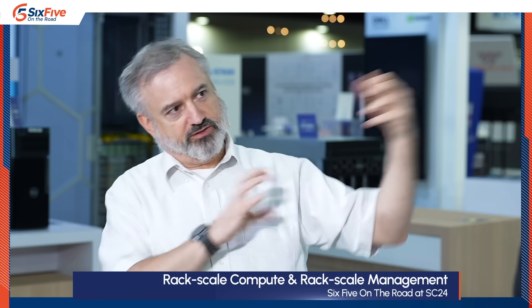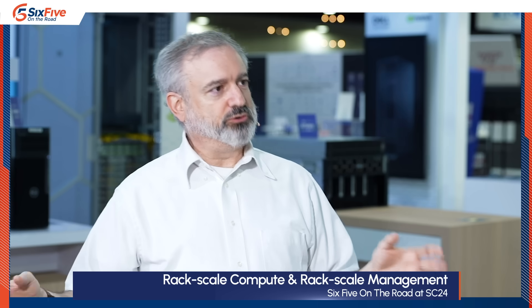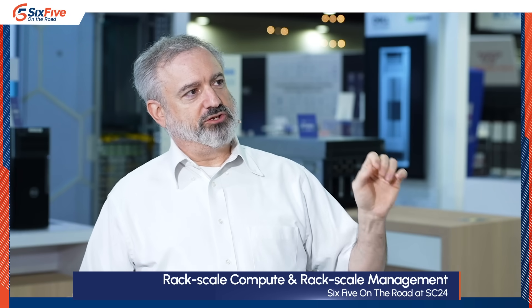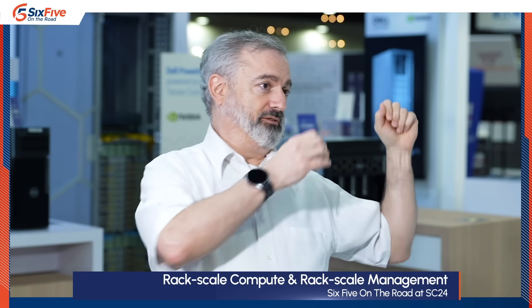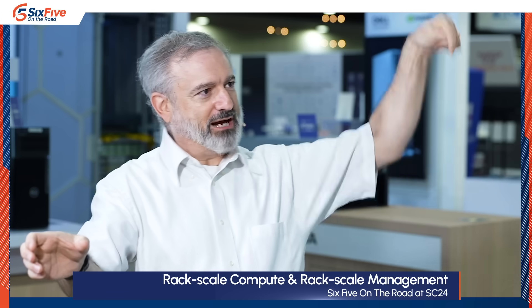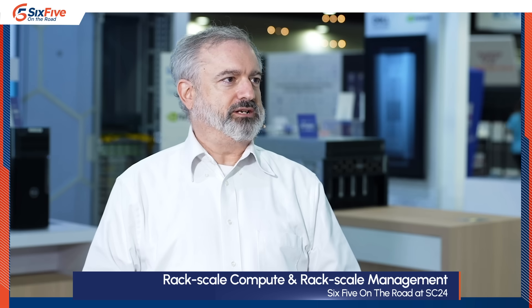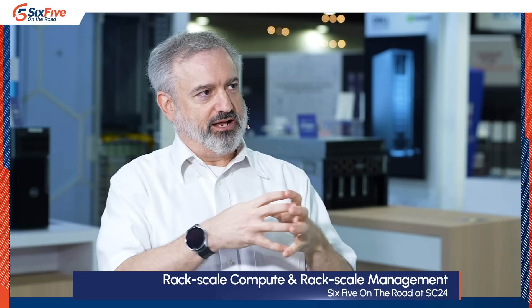Because all of our servers have thermal sensors, we're able to give a thermal view of the front and rear of the rack. But what's really important is: if you've got 10 racks of liquid-cooled gear and one server springs a leak, you want to make sure you shut down the correct rack. If a server has been moved from rack one to rack five and the management system doesn't know that, it will shut down rack one where the server is not, and the leak will continue in the other rack. It's critical to truly understand rack scale — where everything is and what's connected to what.